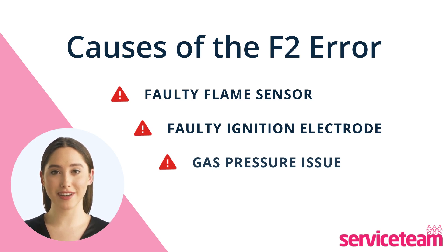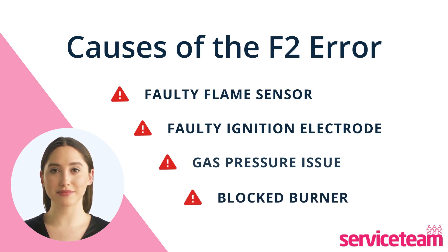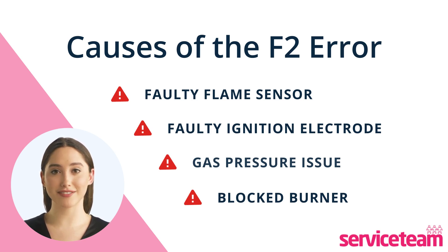The F2 fault code can also occur due to a blocked burner or a clogged heat exchanger. Debris like dust or dirt can block the burner, disrupting gas flow and extinguishing the flame, leading to the F2 code.